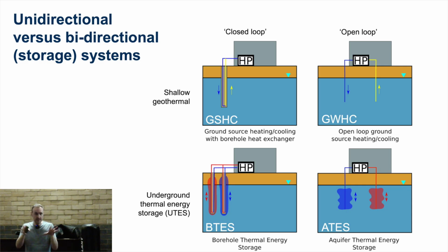Now, if I just use the natural ambient aquifer temperature, I can't really change that. It's 13 degrees or 14 degrees. But if I reuse the waste heat and waste cool, then I can start to engineer it to give higher and lower temperatures for heating and cooling. So the two technologies that use this: one's called BTES, borehole thermal energy storage, and the other is ATES, aquifer thermal energy storage. That's the one I really like, because it's big capacity and very efficient.